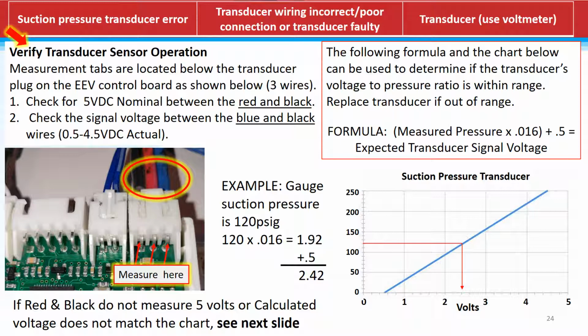We have now eliminated the coil, the valve, the temperature thermistor on the suction line, and now let's check out the transducer. To do that, we need to verify that the transducer sensor has 5 volts DC between red and black. The plug you need to check is on the top right of the EEV board, but under the plug there are 3 bare metal connectors that go from the plug into the board itself. Measure right there. Use your small probe tips on there and you're going to measure between red and black. You should have 5 volts DC.